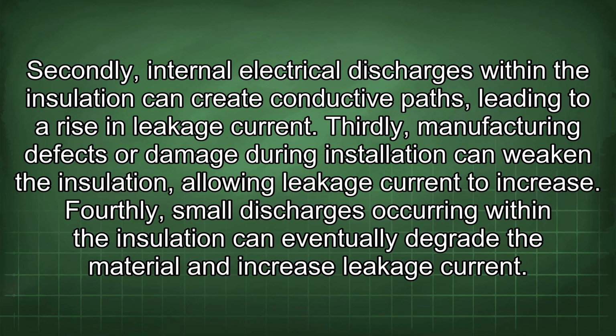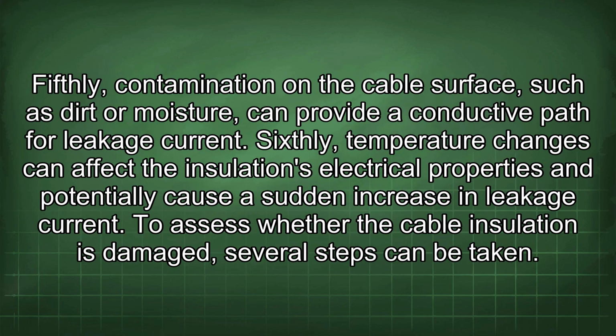Fourthly, small discharges occurring within the insulation can eventually degrade the material and increase leakage current. Fifthly, contamination on the cable surface, such as dirt or moisture, can provide a conductive path for leakage current. Sixthly, temperature changes can affect the insulation's electrical properties and potentially cause a sudden increase in leakage current.